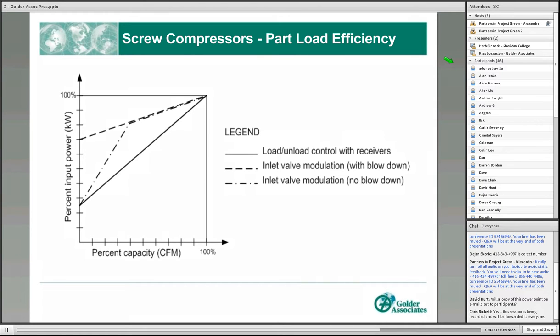And with an inlet valve modulation with blowdown, at zero load or next to zero load, you're still consuming 70% of the power running that machine. So when you're coming into a compressor room and you hear the machine running, you might be producing a very small amount of CFM output and still consuming a lot of power.